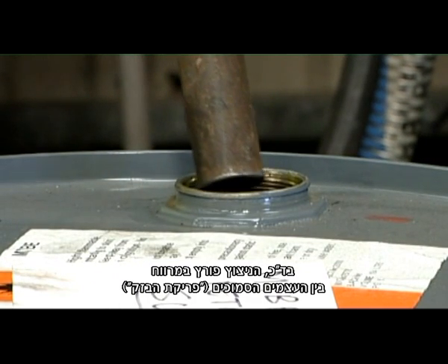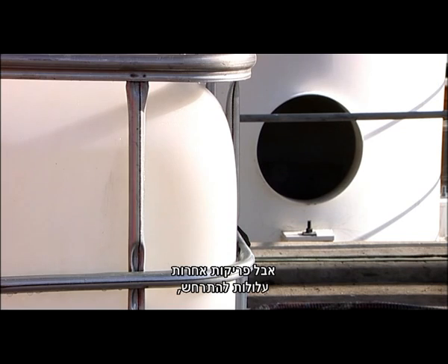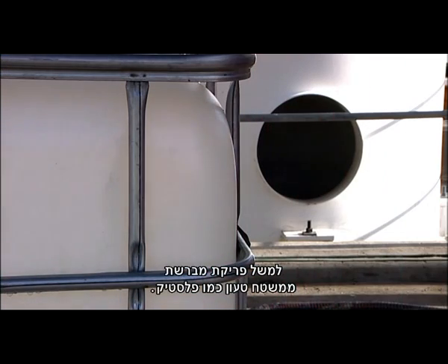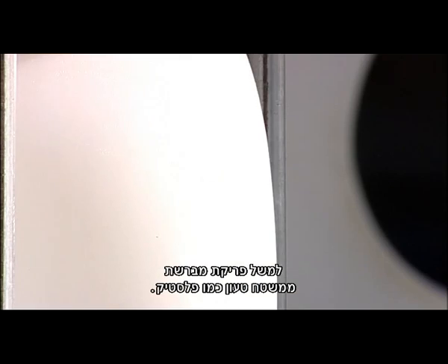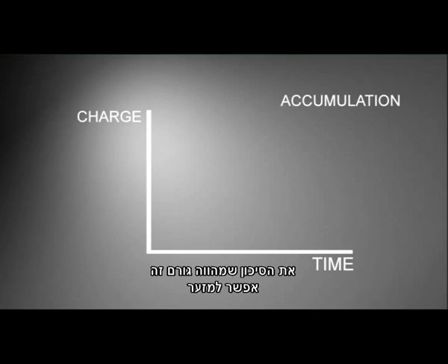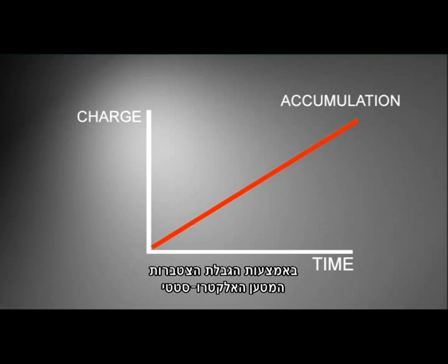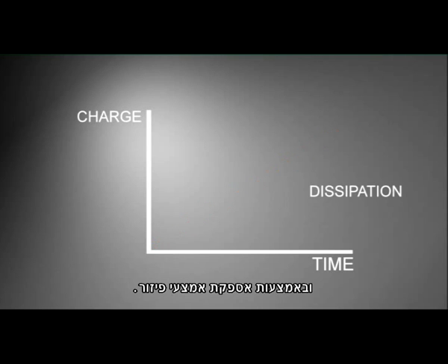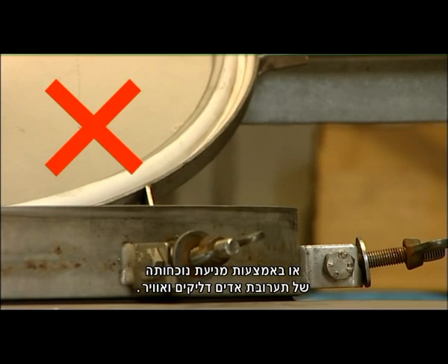Normally, the spark jumps across a spark gap, but other discharges can occur, such as brush discharges from a charged surface, such as plastic. The risk due to this hazard can be minimized by limiting the accumulation of electrostatic charges to safe values, by controlling the rate of generation, and by providing the means of dissipation, or by eliminating the presence of a flammable vapor-air mixture.